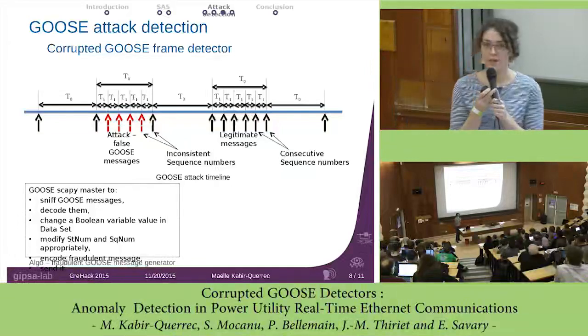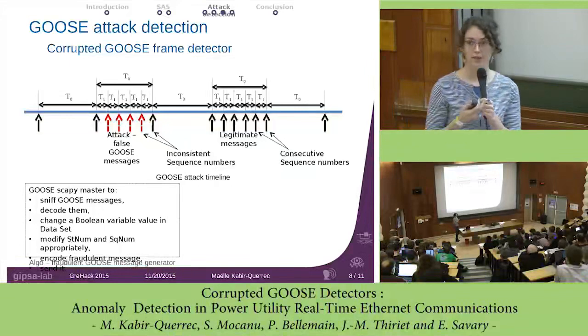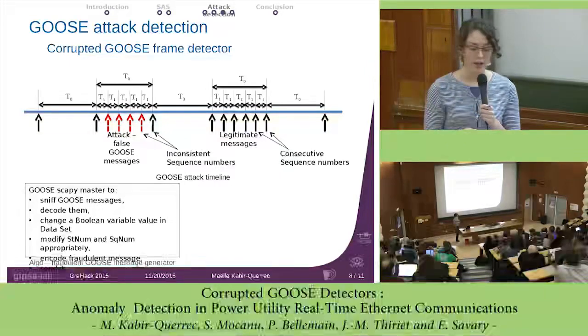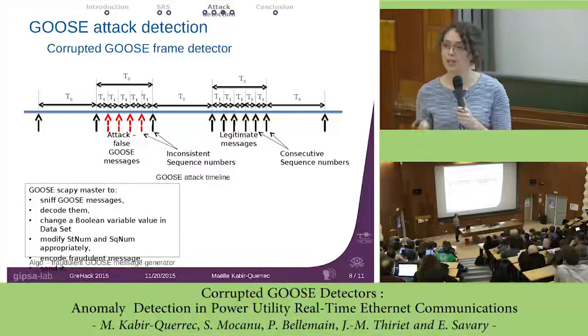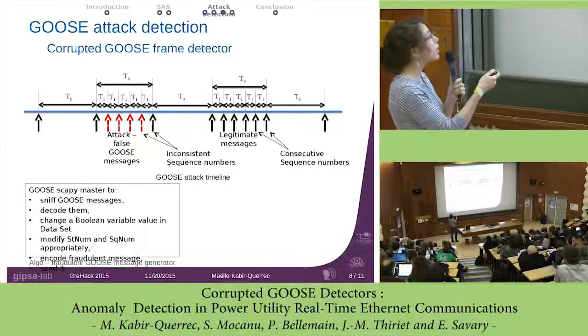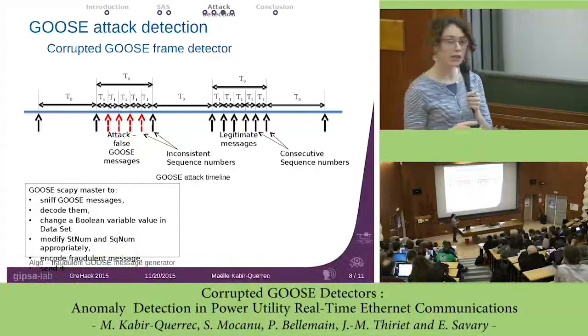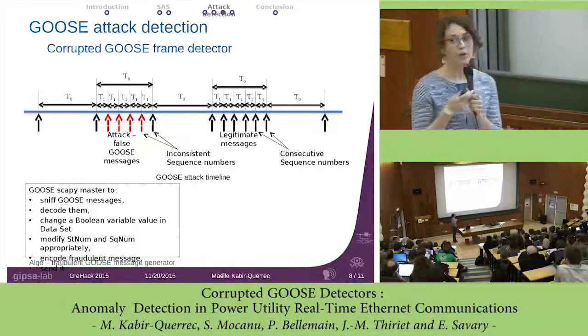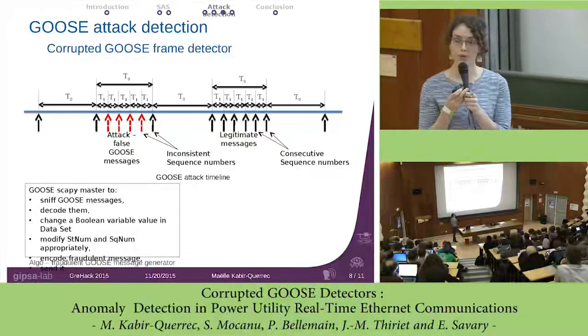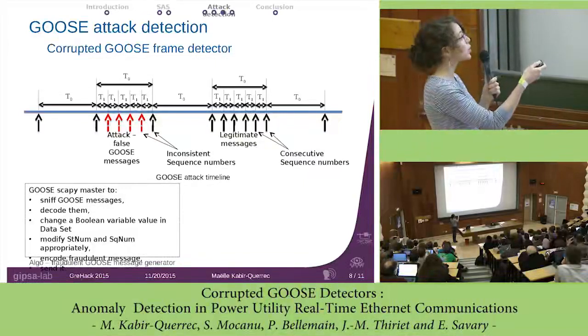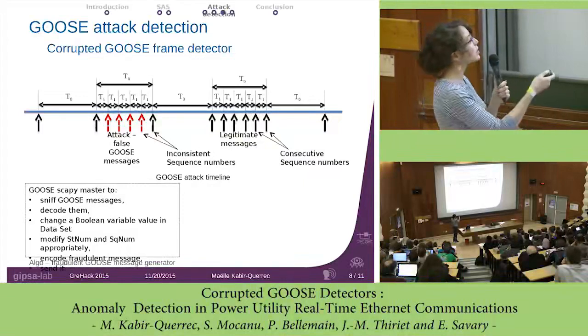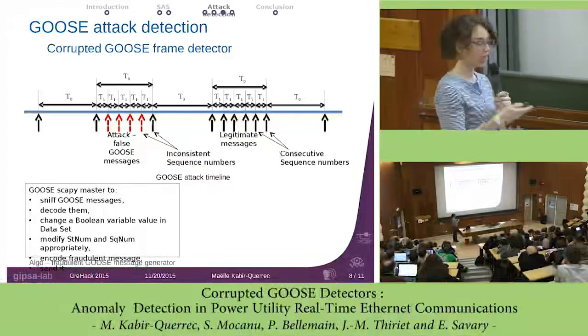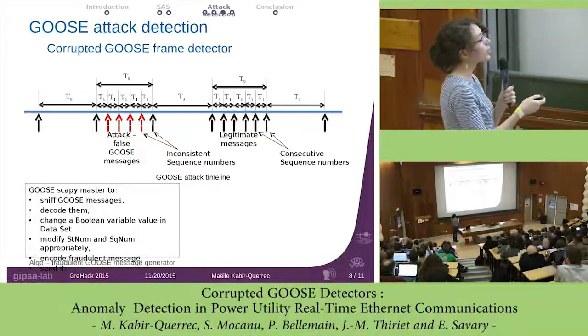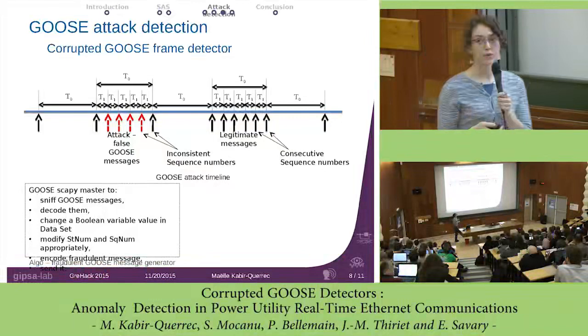Actually, we can detect that, because even if the attacker is very good and the attack is perfect, so it means he will take care of changing the counters we have in the PDU of the GOOSE message, that is the state number and the sequence number. So here, he will take care of incrementing the state number of the dataset, and he will take care of resetting the sequence number to 0, and then increment the sequence number here and here. But when the next legitimate message arrives, it will be detected because there will be inconsistent sequence numbers.